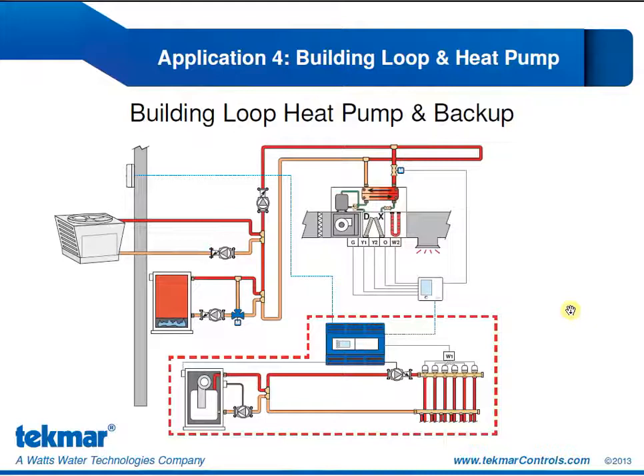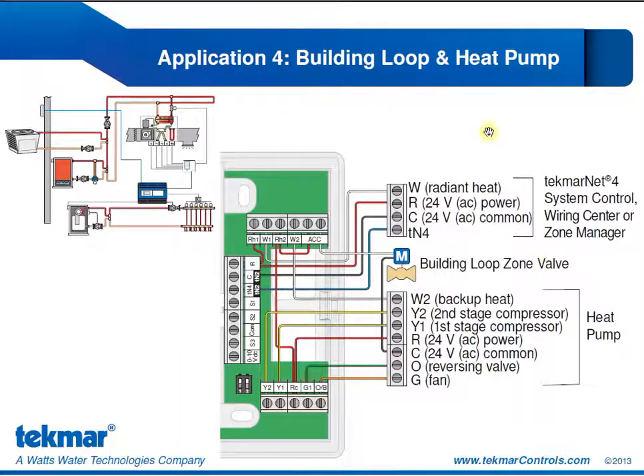So this type of application, usually seen in hotels or conference centers, multifamily residences, apartment buildings, where each unit has its own water-to-air heat pump so that each unit has individualized temperature control. Some can be in heating, some can be in cooling.